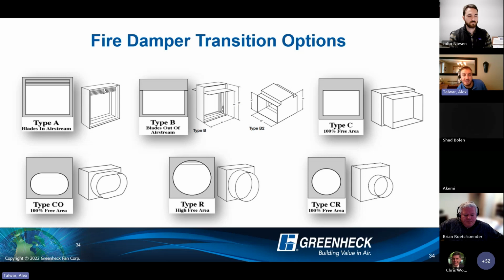In terms of transitions on these curtain style products, the type B is always a popular one. That'll get your curtain stack out of the airstream, increase the free area, decrease pressure drop. Just one word of caution, if you are looking at a type B, just be aware that your H dimension, the height dimension, matches up with the duct, but then your O dimension, the opening dimension in the wall, is going to be a little bit different. So we do have charts for that. You can look it up, but just be aware that there are differences between that H and O dimension when you're making your drawings and things like that. You'll see other shape transitions as well, so square to round and that type of thing.